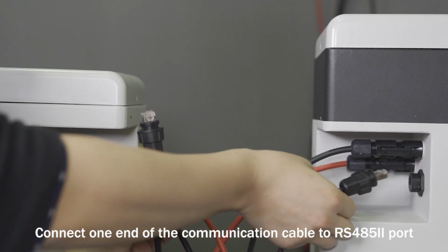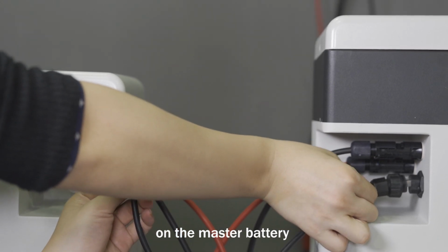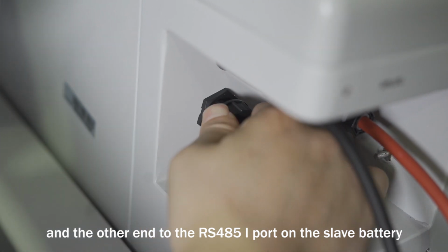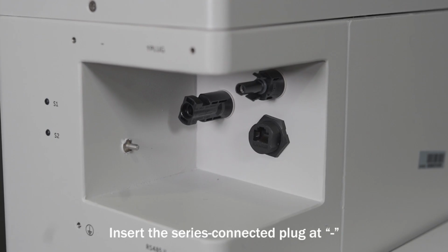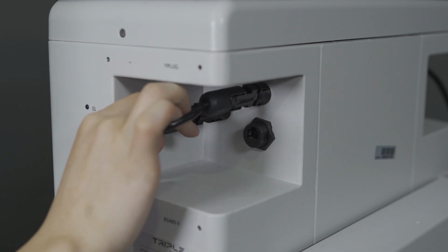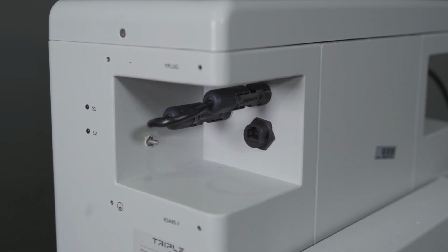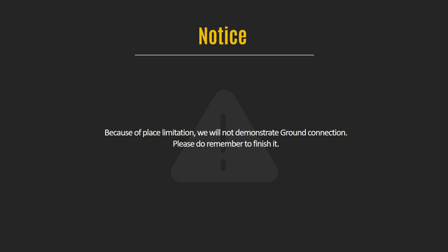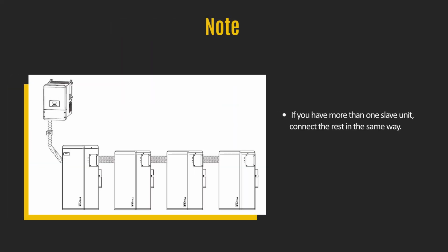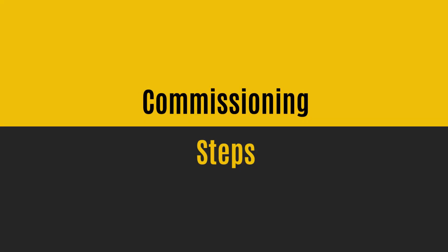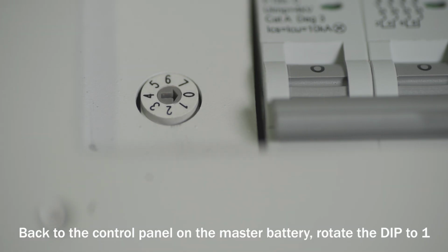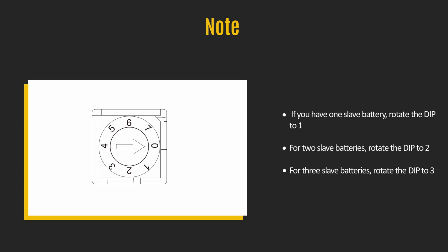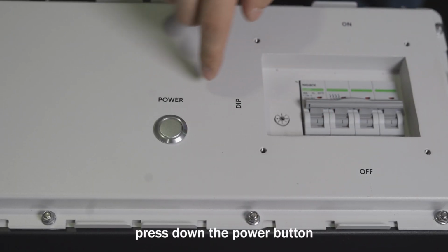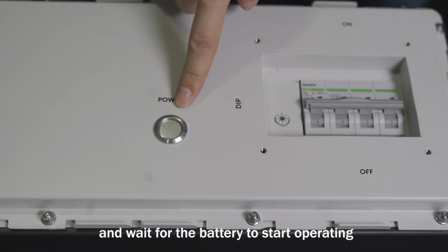Connect one end of the communication cable to RS485 II port on the master battery and the other end to the RS485 I port on the slave battery. Insert the series connected plug at negative and Y plug ports on the slave battery. Back to the control panel on the master battery. Rotate the dip to 1. And switch the circuit breaker to on. Press down the power button and wait for the battery to start operating.